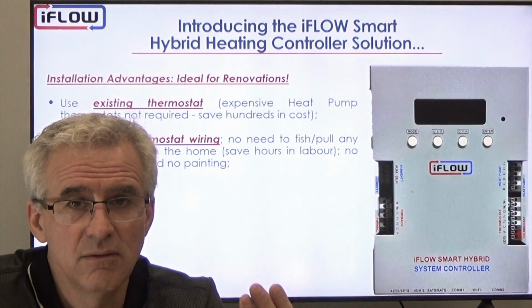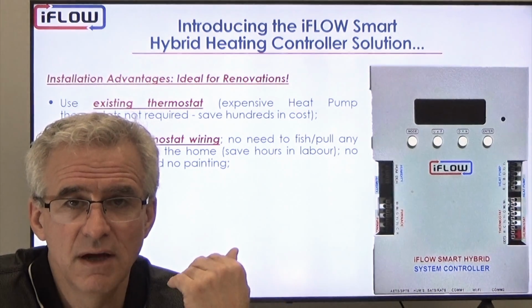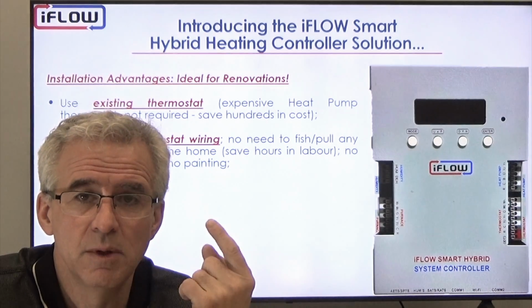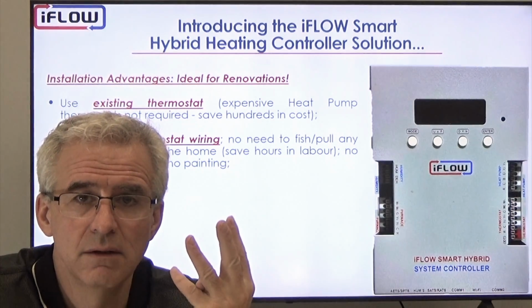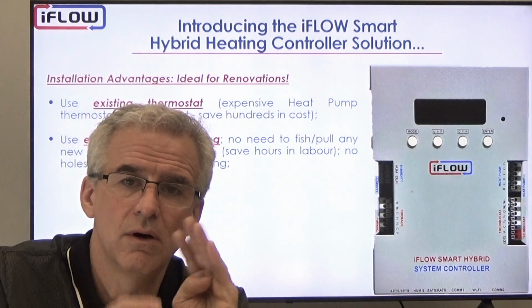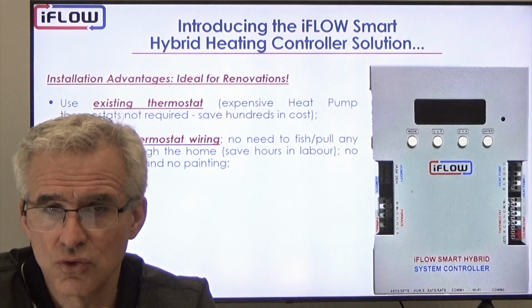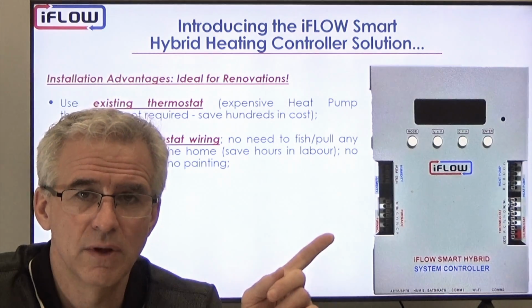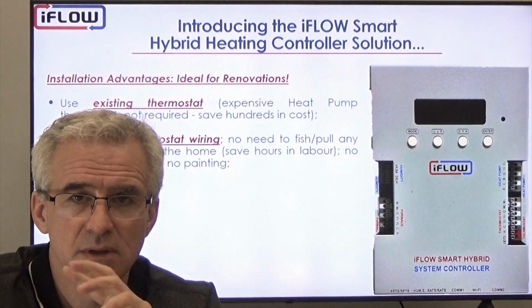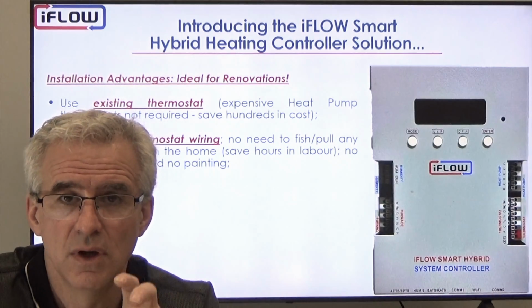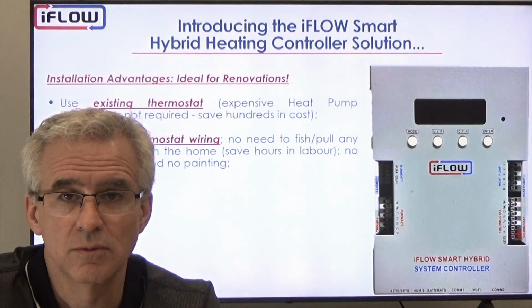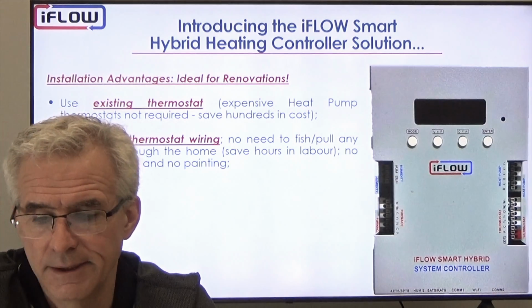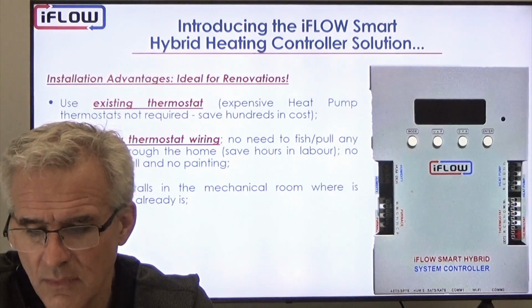Again, we only need 3 or 4 wires coming into the iFLOW, a minimum of 3: R, W, and Y. If we have the heating and cooling call, that's all we need. We will take it from there, and the controller will decide whether we run the heat pump or whether we run the furnace. All of the wiring is connected to our controller in the mechanical room, so we don't have to fish it through the walls of the home.